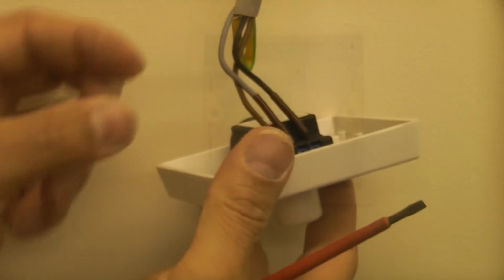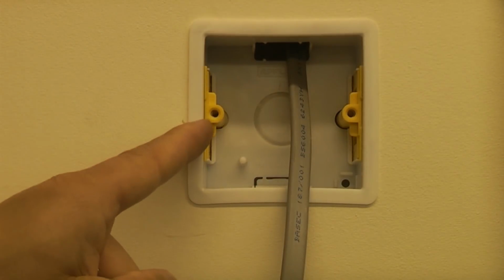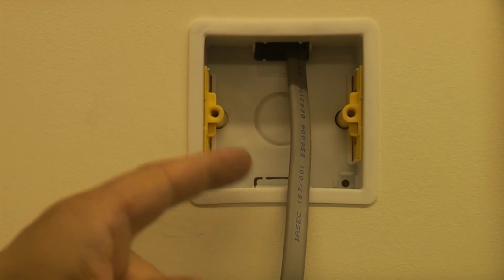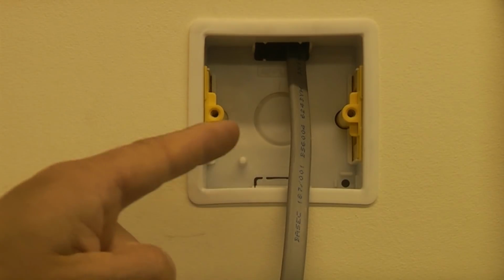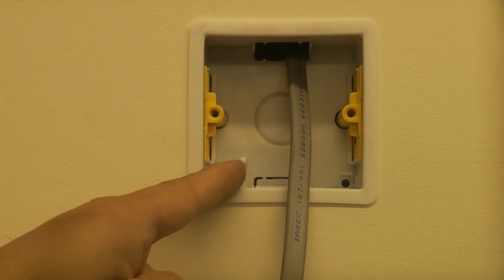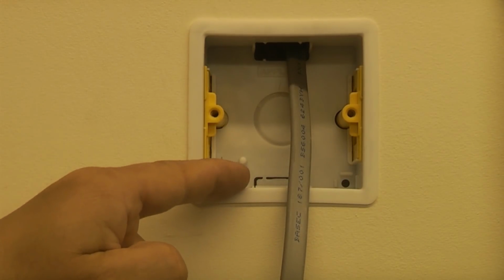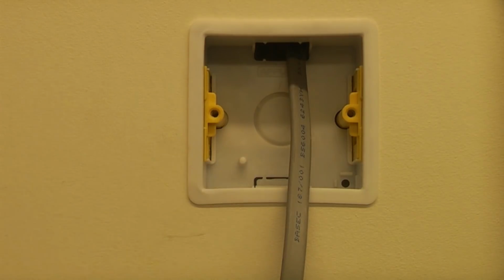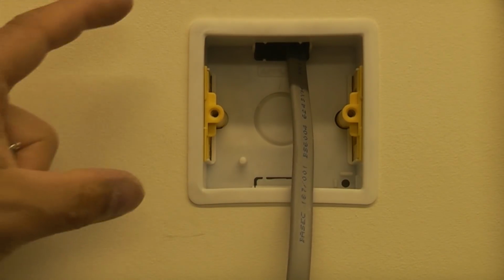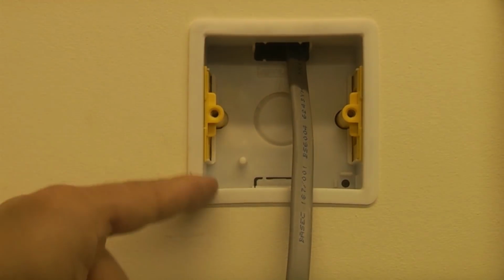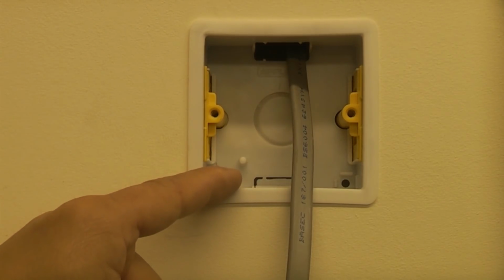Now we've done that, we're just going to pull on the wires to ensure that they are firmly fixed in the terminals. You will notice that this is a plastic back box. It's quite common to have a metal one. If you have a metal one, it would normally be earthed. If it's not earthed, you do have to be very careful about the type of dimmer that you fit. You should only fit a plastic one. Never go fitting a metal switch to a circuit that is not earthed.